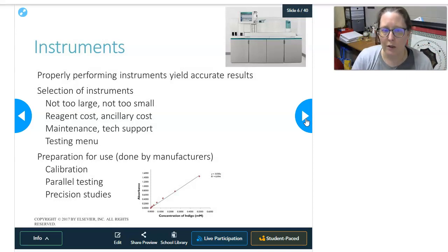You also are going to want to consider the reagent cost and other ancillary costs. So reagent cost is straight up, how much reagent are you using for the test that you're performing? Sometimes some analyzers, like the machine itself, might be low cost, but then they get you with the reagents because you need those reagents, and so the cost is there. Sometimes you can even do reagent rental of an instrument where they basically give you the instrument for free, but you pay for it through the use of the reagents.